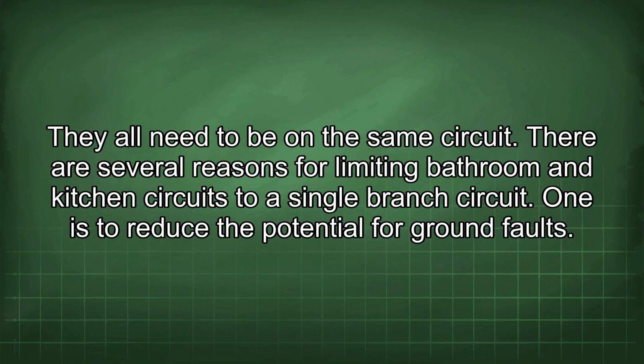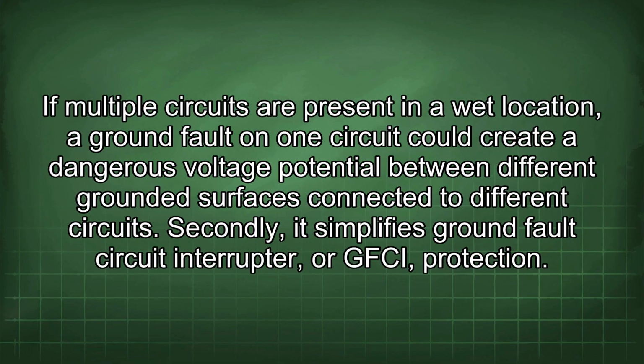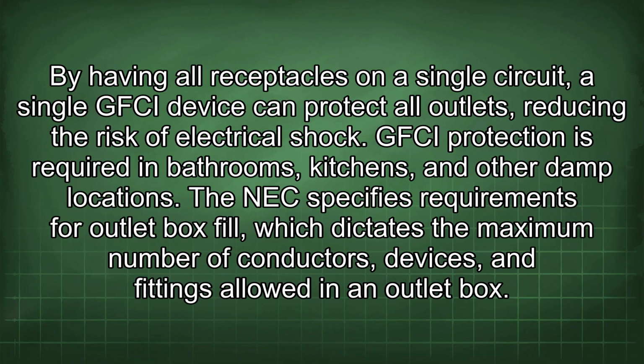There are several reasons for limiting bathroom and kitchen circuits to a single branch circuit. One is to reduce the potential for ground faults. If multiple circuits are present in a wet location, a ground fault on one circuit could create a dangerous voltage potential between different grounded surfaces connected to different circuits. Secondly, it simplifies ground fault circuit interrupter, or GFCI, protection. By having all receptacles on a single circuit, a single GFCI device can protect all outlets, reducing the risk of electrical shock. GFCI protection is required in bathrooms, kitchens, and other damp locations.